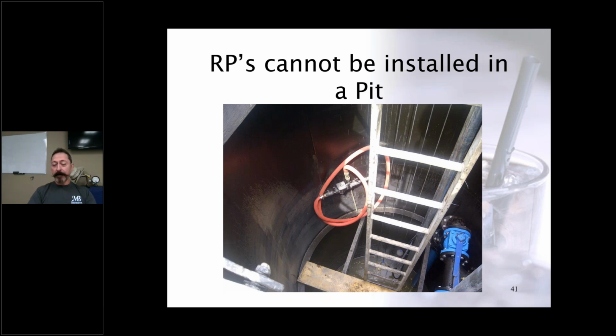This happens to be installed in the wet well in a lift station. So if that lift station is submerged in raw sewage, so is that backflow preventer, and you have a cross connection that is a very severe hazard type of connection. Back in the day, a lot of these systems were engineered that way, to provide a hose bib inside a lift station to wash it out and that sort of thing. But obviously that's a very severe hazard cross connection. Installing a backflow preventer inside the wet well is not the means to protect from that contaminant. So that has to be all dug up and disconnected.